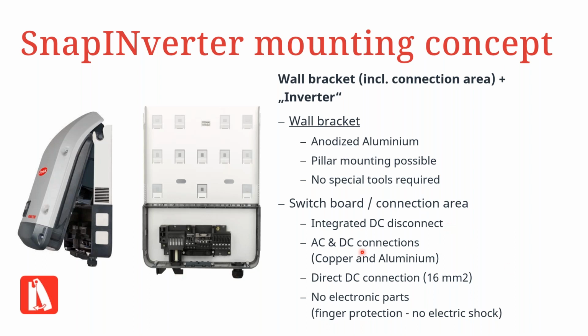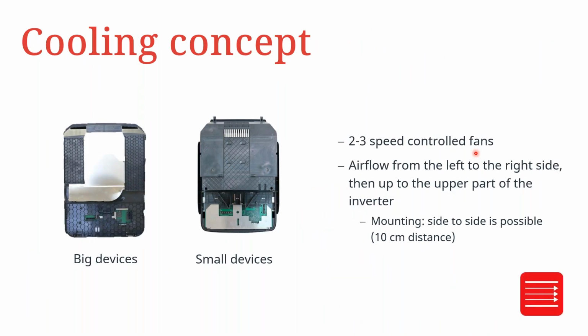And for cabling, you can use both copper and aluminum cables for the Fronius Snap inverters. So that also gives you a lot of flexibility in terms of the cable types to use. The direct connection of cables is up to 16 millimeters square, and within the connection area of the mounting bracket, there are no electronic parts. So it also has some protection against electric shock. So you will not get any safety hazards with using the mounting bracket.